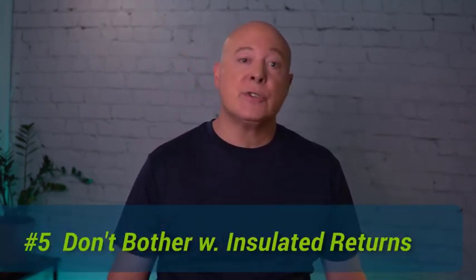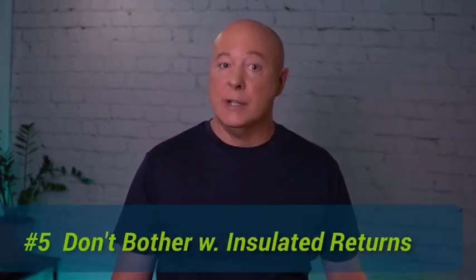Now, one use of thermal imaging with this kind of uninsulated ducts is to help explain the benefit of adding duct wrap. I've often bundled in some basement supply duct insulation with AeroSeal, sometimes just for the long supply branch duct going to a problem room. Their air will come out a bit colder in the summer and warmer in the winter, helping achieve the client's desired outcome. Tip number 5 is don't bother scanning insulated return ducts.